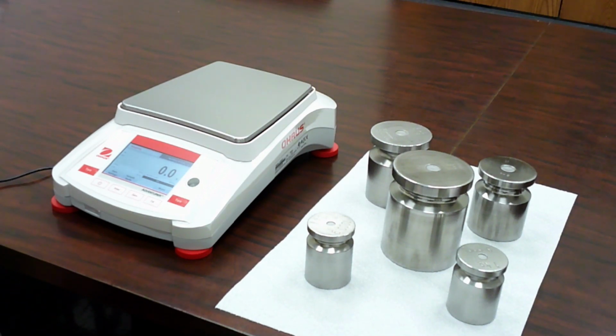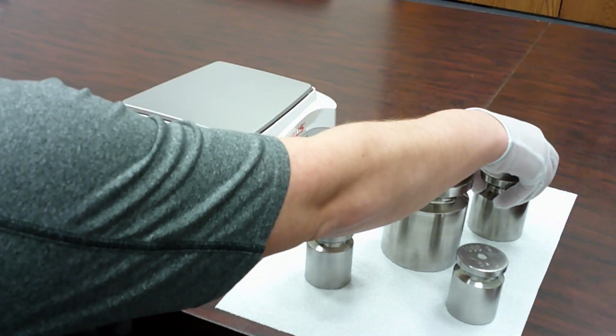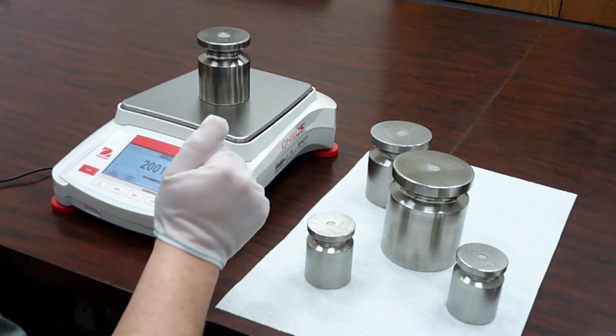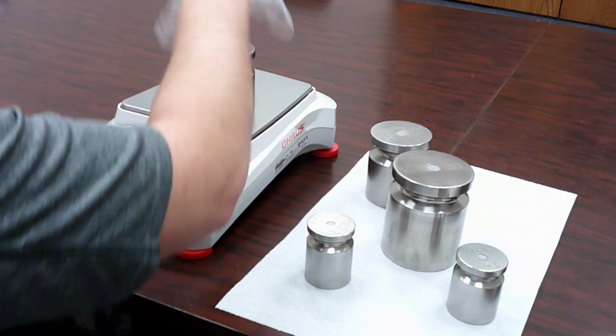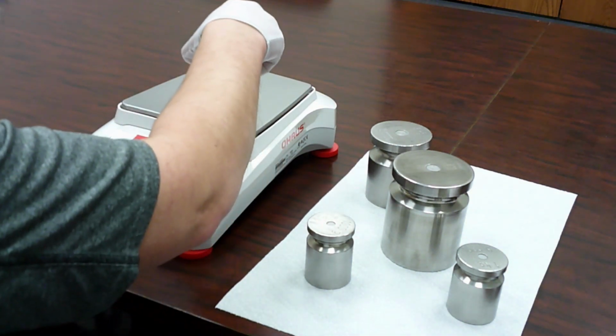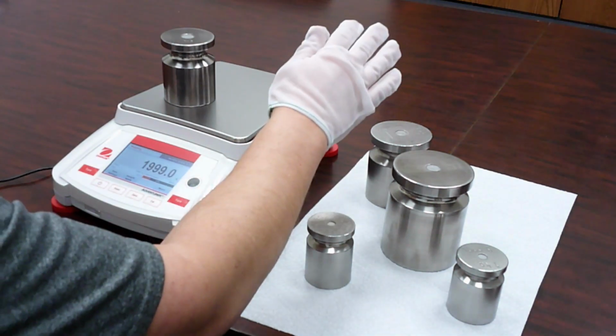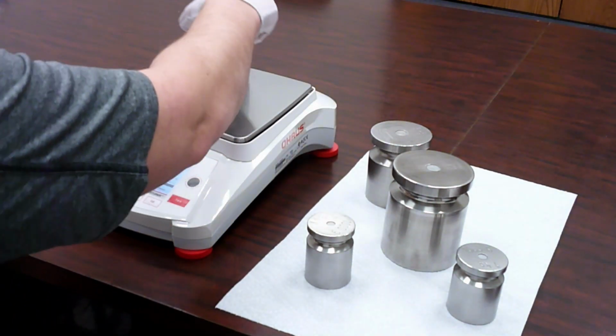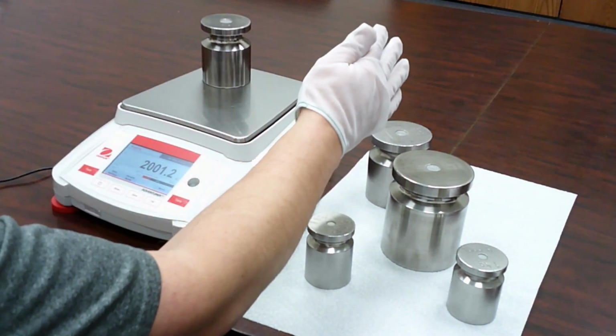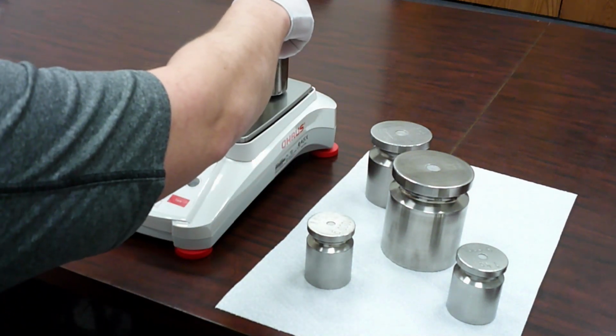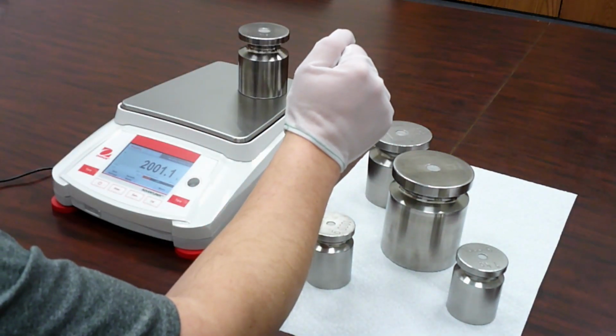often called corner load test. This test will tell us the effects of weight if we are not weighing perfectly centered on the pan. We use the second weight value from our first test. Placing it in the center of the pan, we take our first value there. We then move it equally 50% to each of the 4 quadrants around the pan. We are looking for major errors from one corner to another. If you find an error here, stop and have your equipment serviced immediately.